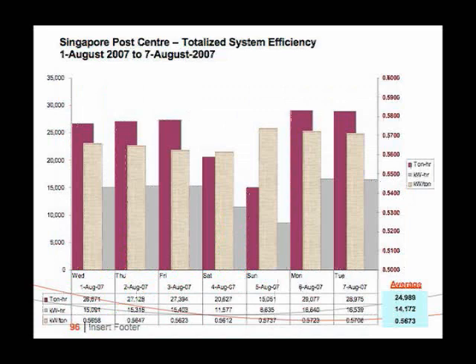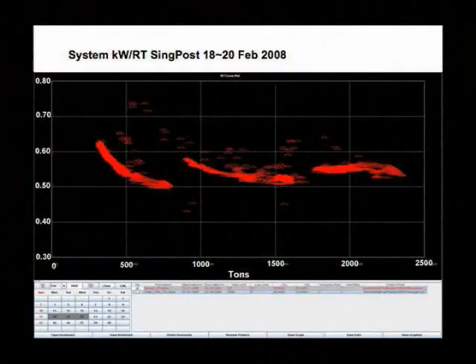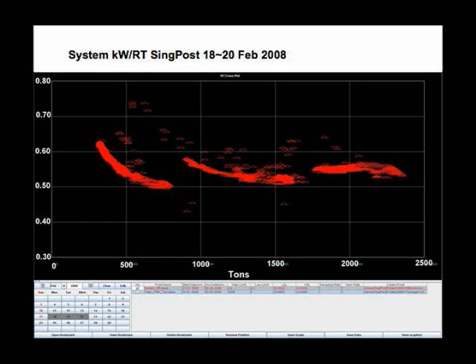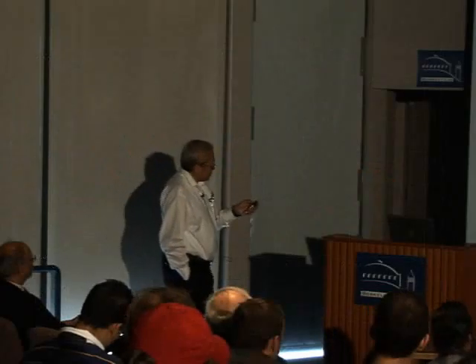And very simple aggregation. For each day, you can get total kilowatt hours, total ton hours, and total kilowatt per ton. And for this week, we are at 0.5673. Some weeks, we are at 0.55. Instantaneously, we can be at 0.5152, but anyway. Another way to represent performance is kilowatt per ton against tons. So we are always at 0.5 something. You've got to be here when new, because in 8 years, who knows?